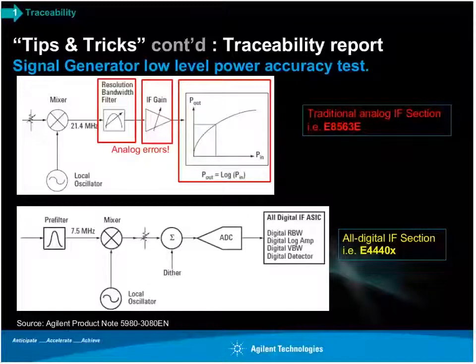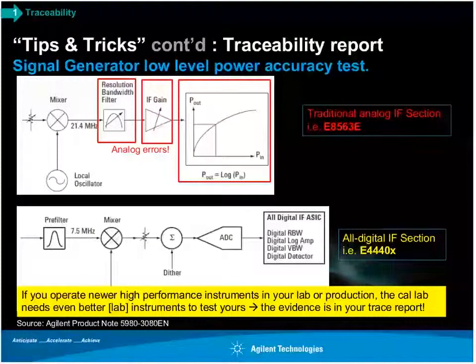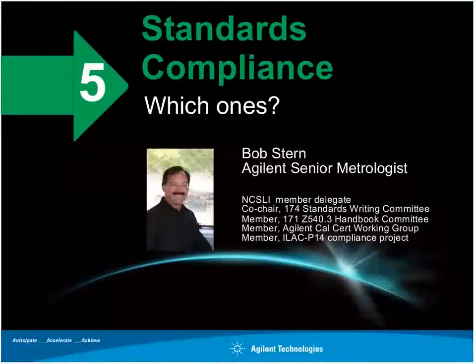It's incredible. There's a little product note reference down there, but it's very possible. And by the way, the Agilent measuring receiver that you saw in the Army flow diagram is obviously depending on a spectrum analyzer which has one of these digital IFs. The point I wanted to make here is the following. If you're operating any of the newer high-performance instruments from Agilent, or for that matter anybody else, in your laboratory or in your production test systems, the lab standards used in that calibration lab, the only way they're going to be able to measure your instrument properly is if they're at least as good, if not better, than what you're submitting. And the way that you would know that is if you can check the trace report.